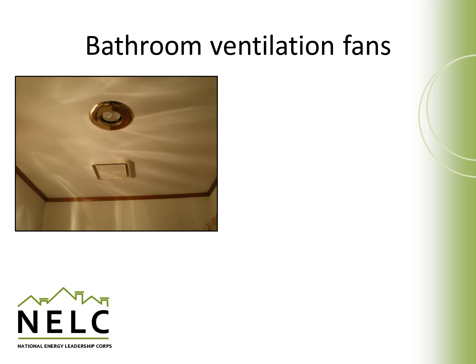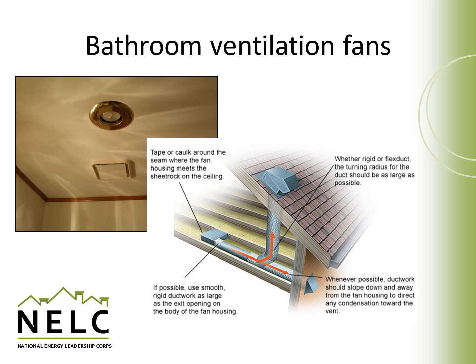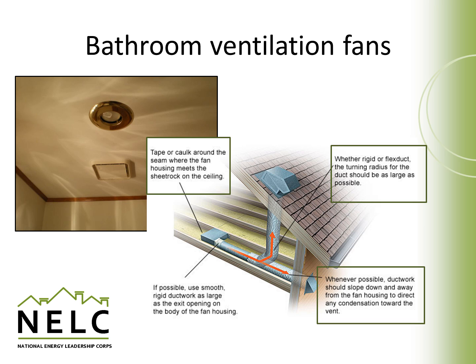A bathroom fan is most common and sometimes it's the only method of mechanical ventilation found in an older home. To make sure it's done properly, the fan itself should be caulked around the perimeter so that when it's not running, it doesn't leak air up into the attic space. The ductwork used should ideally be rigid and the turning radii shouldn't be too tight, to make sure the fan can work properly. When possible, it should be sloped away from the fan to avoid condensation running back into the vent, and smooth, large ductwork should exit straight out to ensure good airflow.